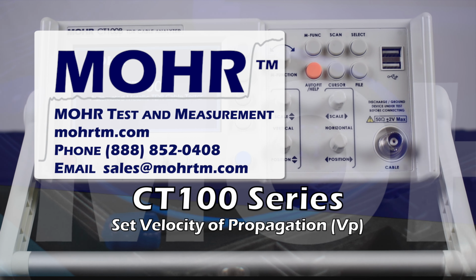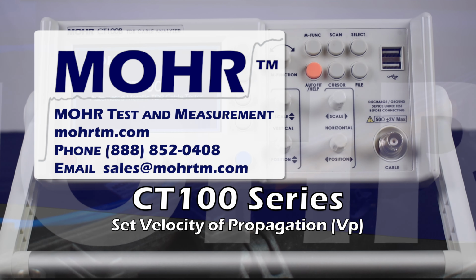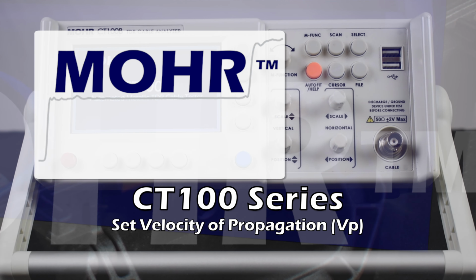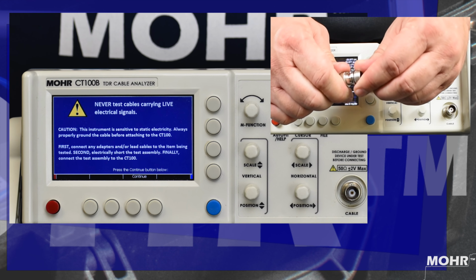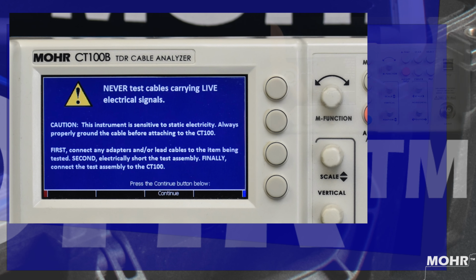Today we'll be showing how to set the VP, or Velocity of Propagation, with the MOHR CT100 series TDR. Let's get started. Always remember to properly discharge static before connecting to any high-frequency test equipment, and never connect to live equipment.